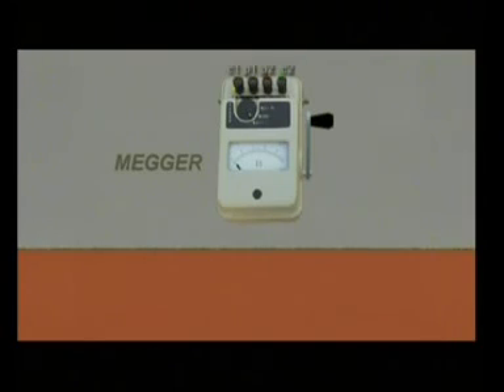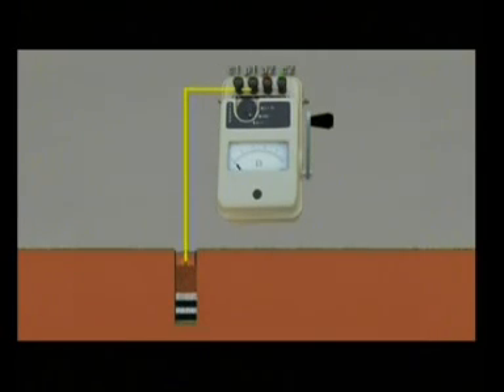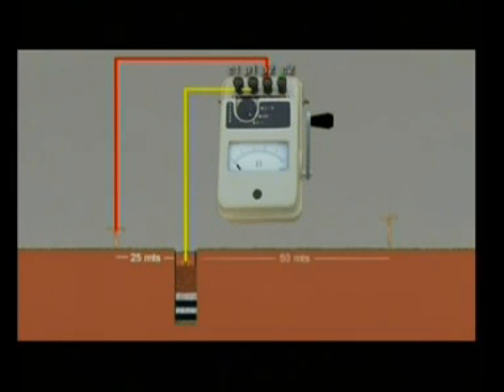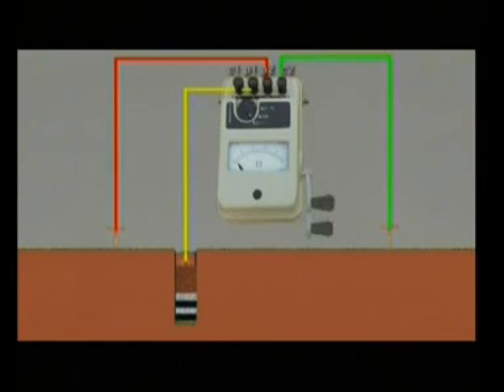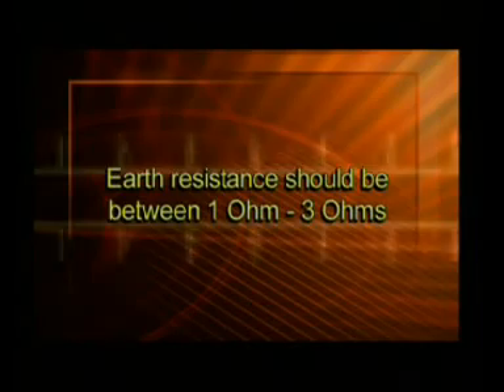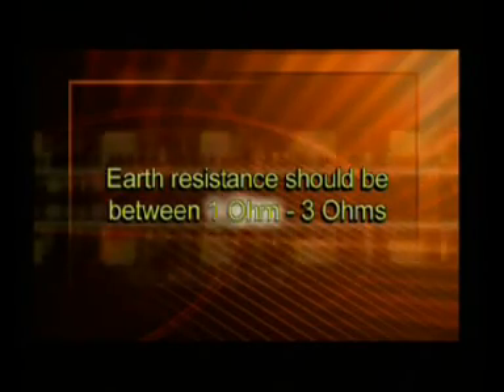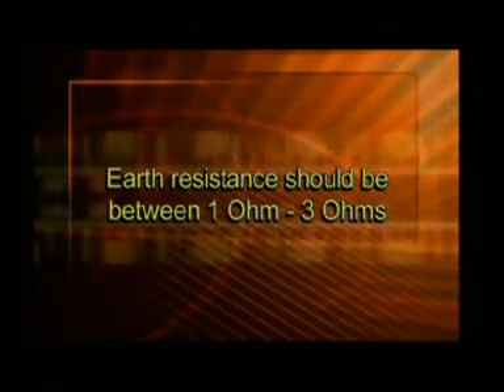As demonstrated, C1 and P1 terminals are connected together and then connected to the earth electrodes. Next, terminal P2 is connected to the spike which is at a distance of 25 meters from the earth pit. Terminal C2 is connected to another spike which is placed at a distance of 50 meters from the earth pit. Then the handle of the earth megger is rotated at a speed of 160 rpm. The dial of the earth megger displays the earth resistance. The earth resistance should always be between 1 ohm and 3 ohms.